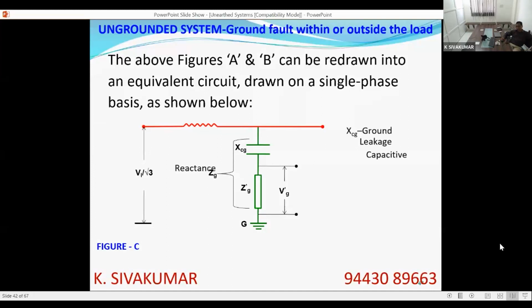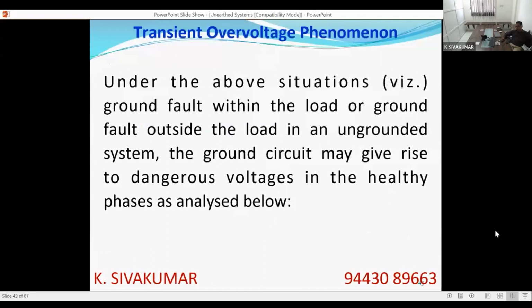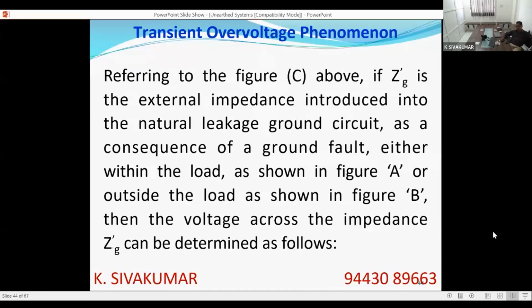Now we have three possibilities. If Z dash G is a resistive impedance, if Z dash G is an inductive impedance, if Z dash G is a capacitive impedance. We will see what are the various transient over voltages developed under these three conditions. Under the above situation, ground fault within the load or ground fault outside the load, the ground circuit may give rise to dangerous voltages in the healthy phases. The first situation is ZG, the external impedance introduced in the natural leakage ground circuit as a consequence of a fault either inside the load or outside the load. Then the voltage across the external impedance can be calculated as per this formula.